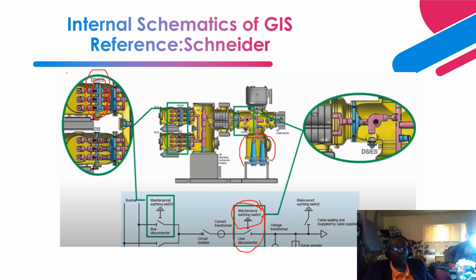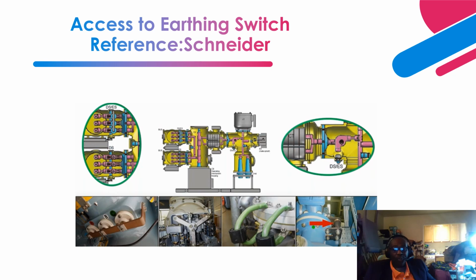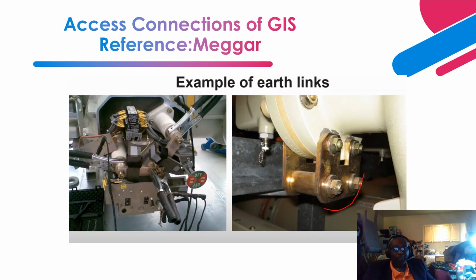This location shows you your feeders, and this is how your line side cables are connected into this apparatus portion. All this side is filled with SF6. On this side is the air side, and this is the PT. This picture also shows different connections for the earthing switch from different manufacturers, and how they are connected. Another picture shows how this earthing switch has been removed.